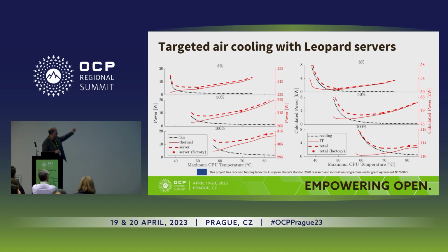Irrespective of whether it's running at 8%, 50%, or 100%. And because we can do that, we could then measure the power draw of the server and the power consumption of the fans. And then that's one server, but then when you put all the servers into a data center on the right there, you can see that actually, once you bring the cooling system into control, the black curve is actually much bigger. So running the fans at high speed, that's the whole reason why we want to slow things down. And so you can see there's a sweet spot of operation.